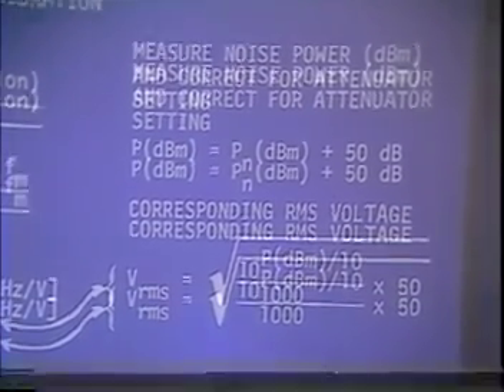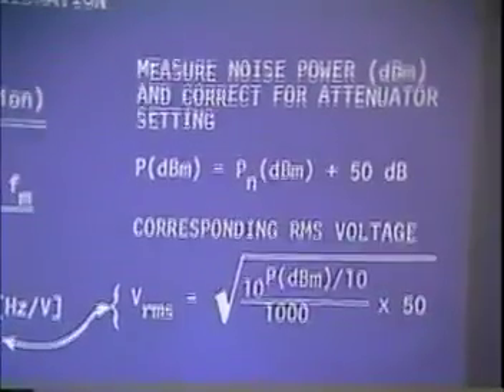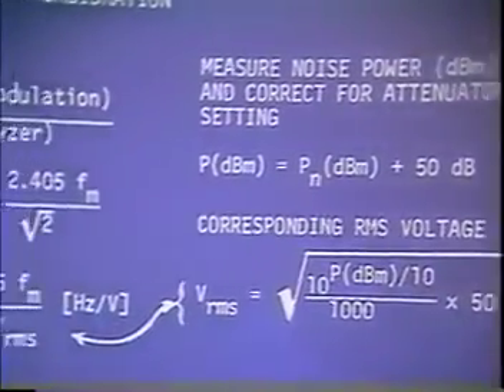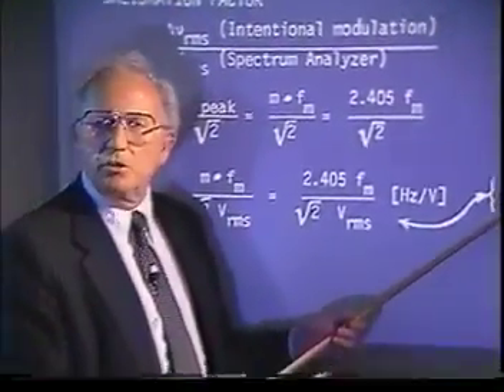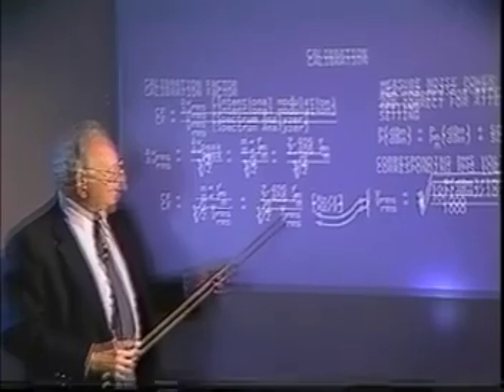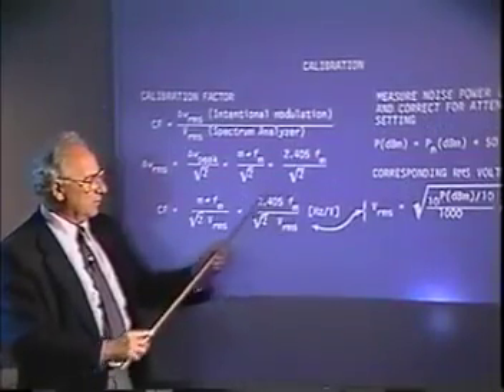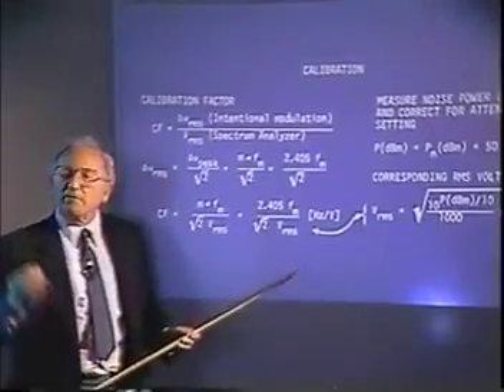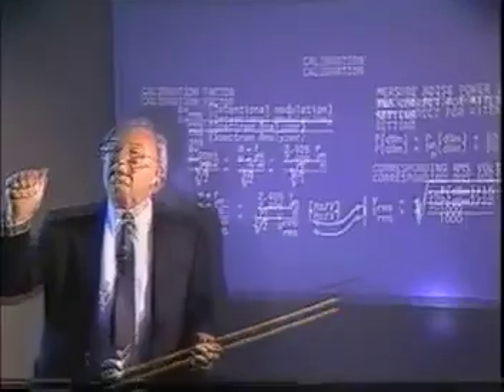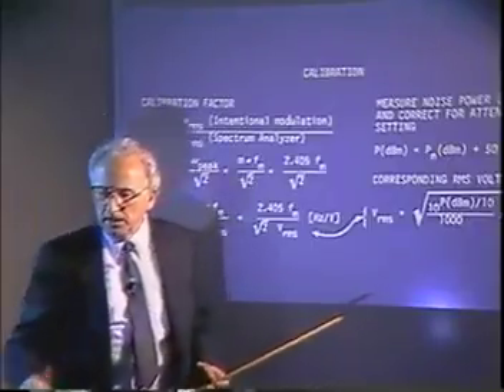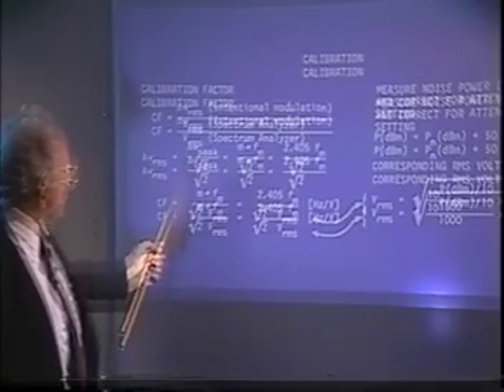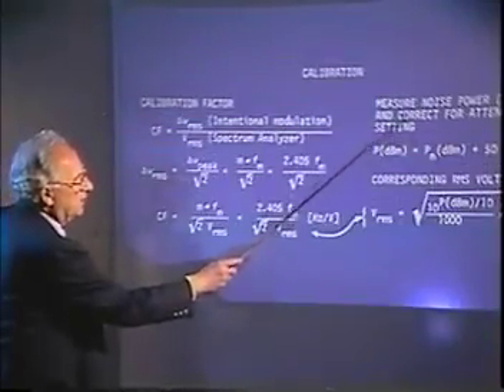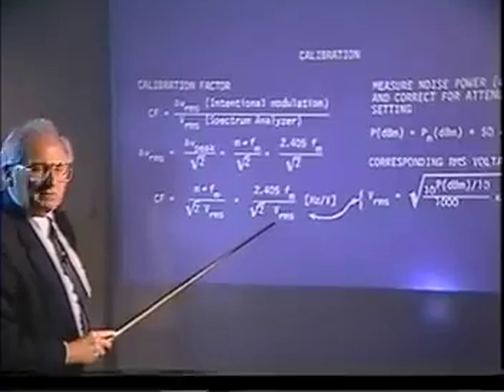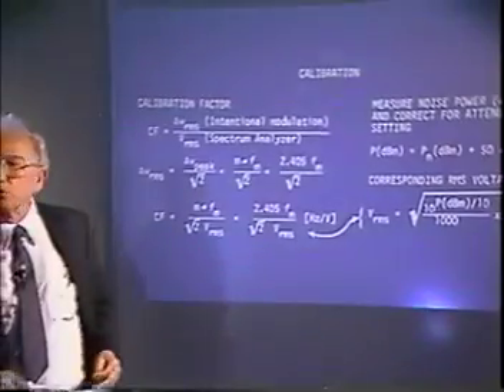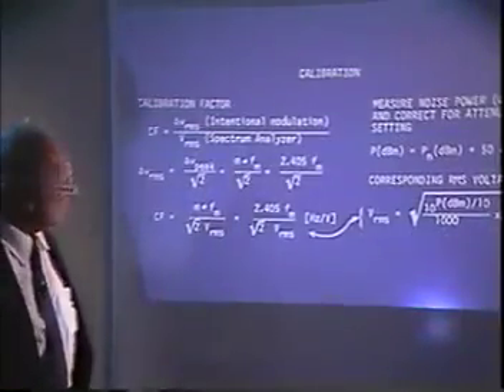That's the output voltage that you measure, because remember in our other system we measured power in dBm? In this case you have to measure power in dBm, but you convert that to voltage, and you use that in these equations here in our program. And this then is the calibration factor. This whole equation here, hertz per volt. So now you have a calibration factor in hertz per volts. That's the value that Hewlett-Packard calls K sub D. All right, now that's the way it's done then. You measure the noise power, dBm, correct for the attenuator setting. So then you have this value for the actual value, VRMS. Now that's measured straight through by modulating and looking at the signal in the spectrum analyzer and measuring it.